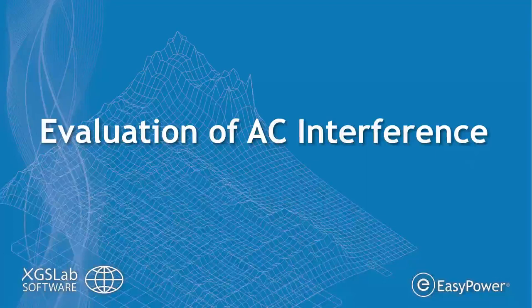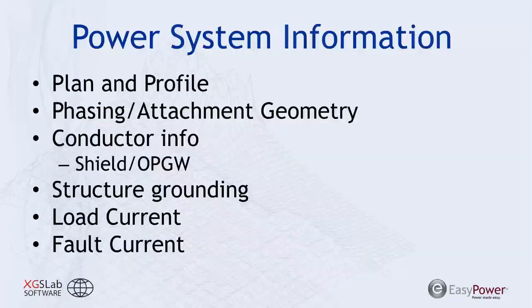So let's talk about the analysis process for AC interference. With most engineering studies, we're going to start with the data. And for a power system, we're looking to understand how the phases are oriented, or the geometry of your phase conductors. We'll want to understand how those propagate along with the plan and profile. You'll also need to know the shield wire information and OPGW wire, if it's applicable, what it is made of, and its physical dimensions. And again, the geometry in relationship to the phase conductors. You may need to know the structure grounding, the designed grounding target impedance, or you could be looking at the installed system of any sort of existing facility or existing transmission lines.